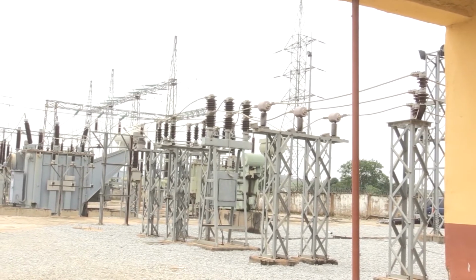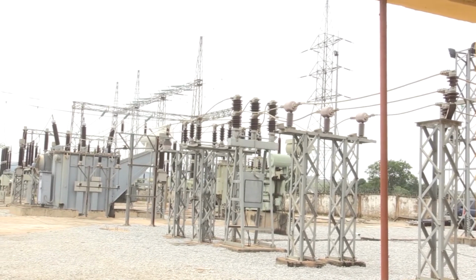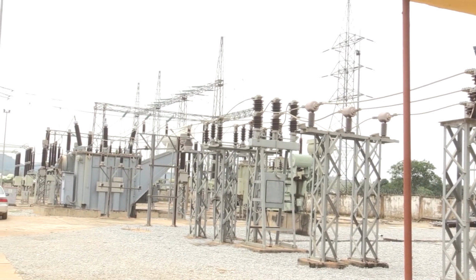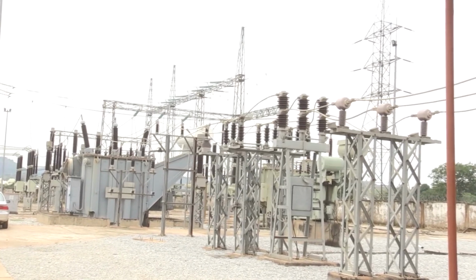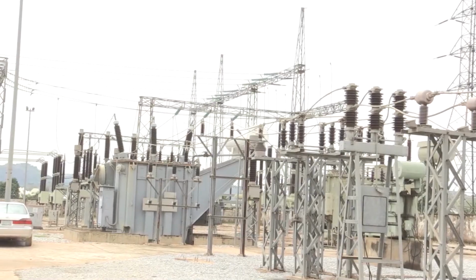For instance, one of the industrial feeders, the Abuja Steel Feeder, was limited to less than 10 megawatts before the installation of the 2 by 60 MVA transformer. Once management installed it, they are now picking more than 16 megawatts, which is a very good improvement.